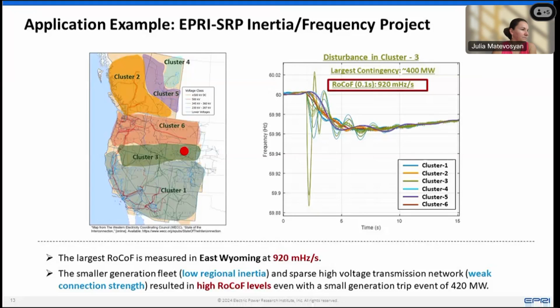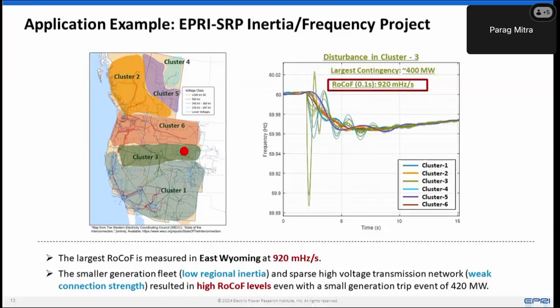When you measure rate of change of frequency on a bus, you're measuring the rate of change of angle. Angles are not state variables, so they tend to change very quickly. Normally, when you measure it, you want to base some action on it, like a protection action. Typically a 100 millisecond or 500 millisecond threshold is chosen because that's the filtering that exists in most protection devices, which is why 0.1 second was used.